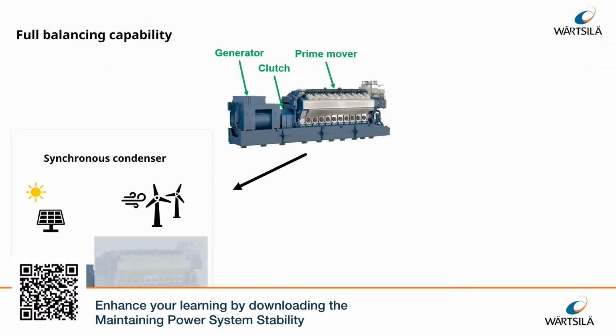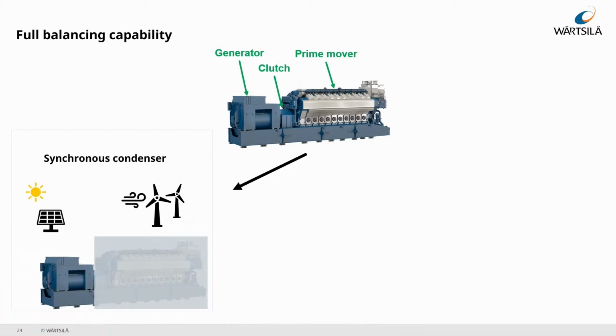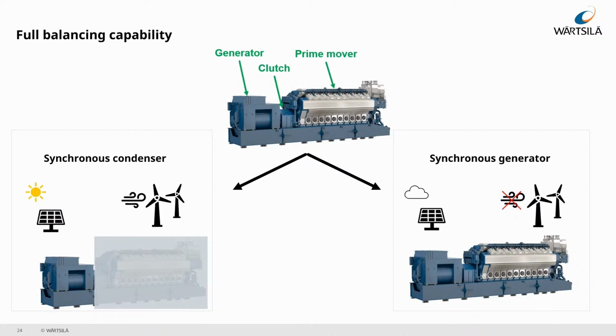For example, when the sun is shining and the wind is blowing, with a lot of renewables in the system, you only want the generator connected, acting as a synchronous condenser. It will provide the inertia we were talking about and the short circuit capacity. But when a cloud covers the sun or there's no wind, you connect the clutch between the engine and the generator, and it will then act to provide power. It will also provide short circuit capacity to the system, and this gives you a source for the restoration plan if something were to happen.